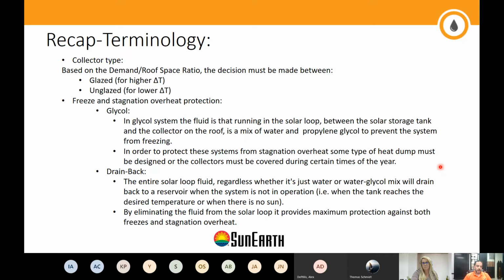But in another application, when you have a large demand coming up at a certain time of the day, for example, if you have a facility that uses a lot of hot water for cleaning at the end of the day, for example, farms, dairy facilities, breweries, they use a lot of hot water for cleaning at the end of their shift. So what you want to do is design a system that can actually collect the heat throughout the day and have it ready for dispensation when the time comes. So now you have to design the proper storage accordingly.